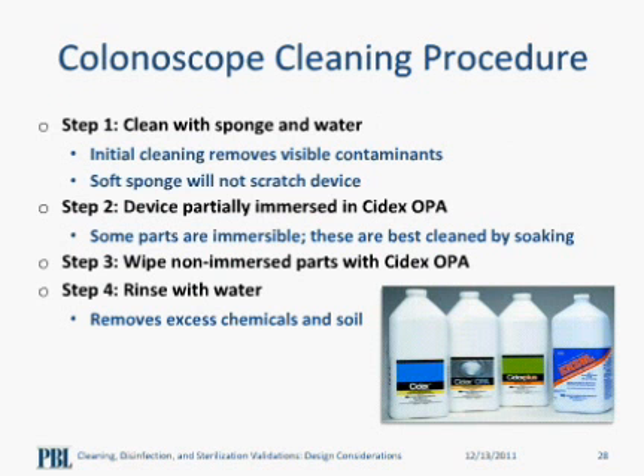This device is cleaned using a lint-free soft sponge to avoid scratching. Wiping with a sponge and water will also help in the removal of visible contaminants. The long flexible tube is immersed into Cidex OPA while scrubbing it with a soft sponge. Partial immersion accommodates the limitations of the device, yet still allows high efficacy of the cleaning procedure.